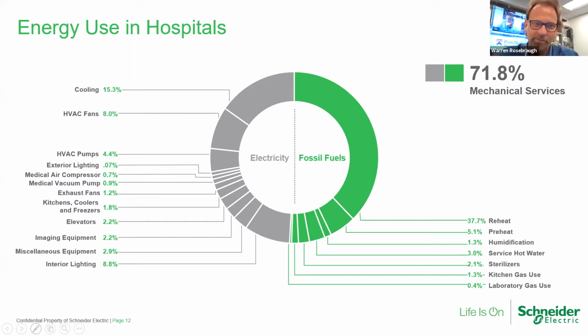72% of the energy spent in a hospital, as published by ASHRAE, is around mechanical systems. Looking at it, 15.3% is to cool the air and take out humidity, 37.7% is for reheat, to do those 7 air exchanges required in a patient room per code, per ASHRAE 170, or the 25 air exchanges needed in an OR. That's about reducing infection control, and it's quite interesting.